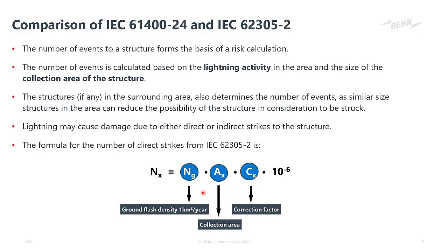The collection area is the area that the building or the structure takes up, and we see how much this area fits into a single square kilometer to determine the number of strikes to that structure in a given year. It's also important that the structure may be surrounded by other structures of similar heights, or smaller, it could be on a hilltop, it could be isolated, and that is known as a correction factor, and it adjusts the number of strikes. So the standard says if there is another structure next to me which is the same height as me, there's a 50-50 chance that either of us will get struck. So this factor becomes 0.5. So we halve the number of strikes between the two of us.